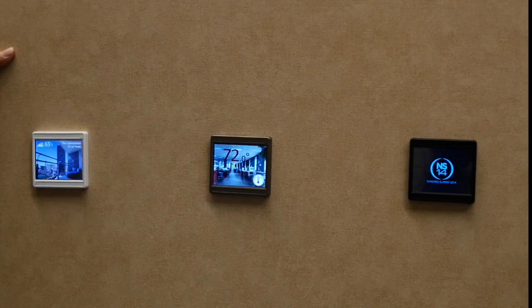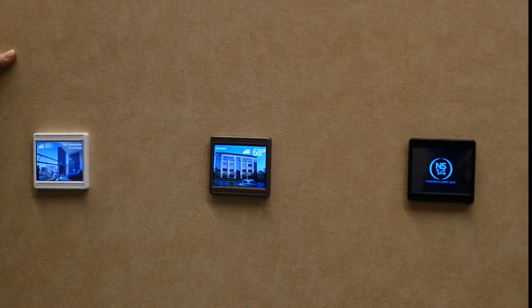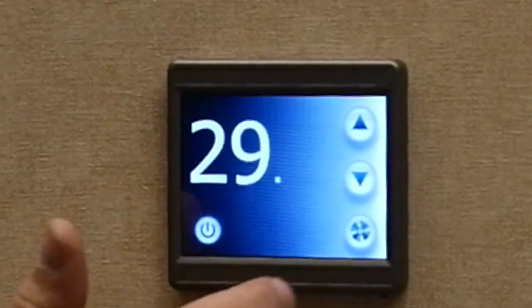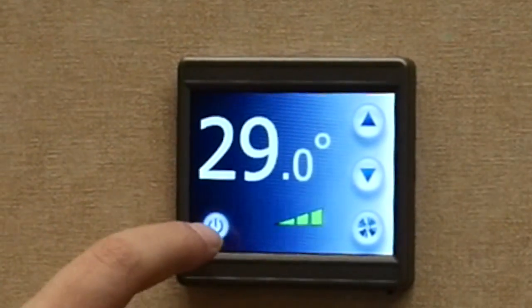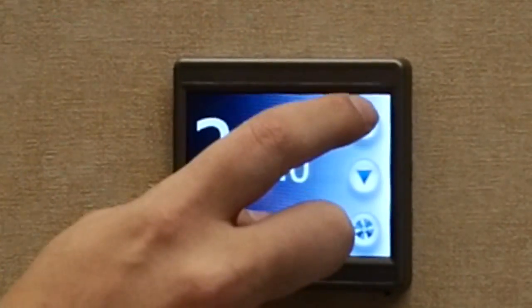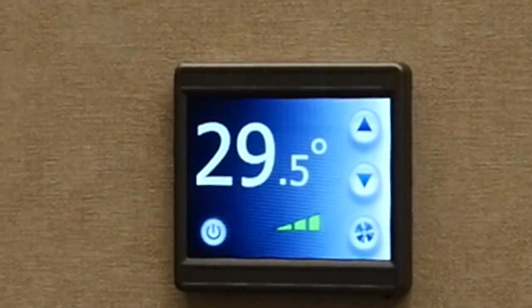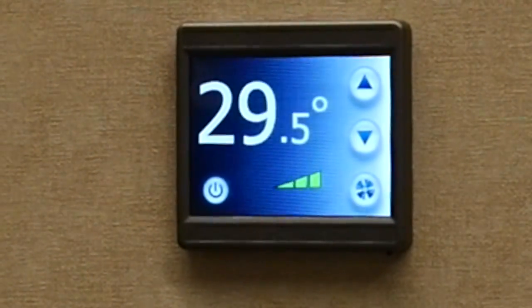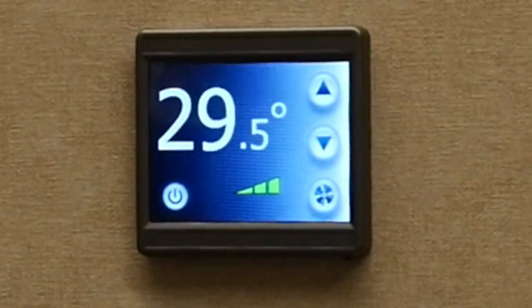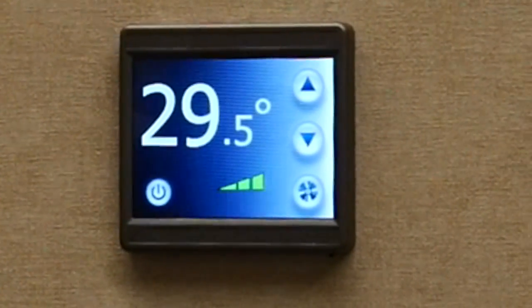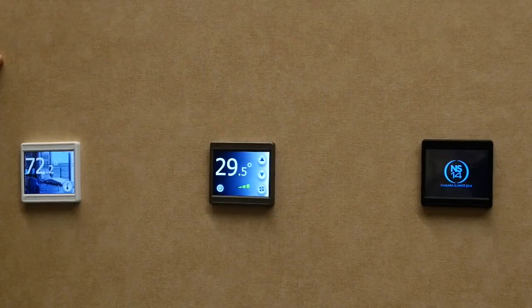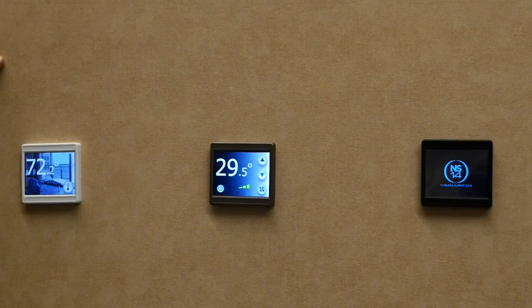All right, well, let's take a look at some of your new products. Great. These are our Ion thermostats. This is basically built with the Sedona framework. And the interesting part of this is the interface is created with PX. It has its own special widget, and it gets compiled and pushed into the thermostat. It has a remote I/O with a proprietary link, and it's great for applications like handheld units, VAV boxes, and terminal units. The price point is pretty good for what it does. It has Modbus slave, so you can grab data from Modbus or Sedona and map it to the screen.